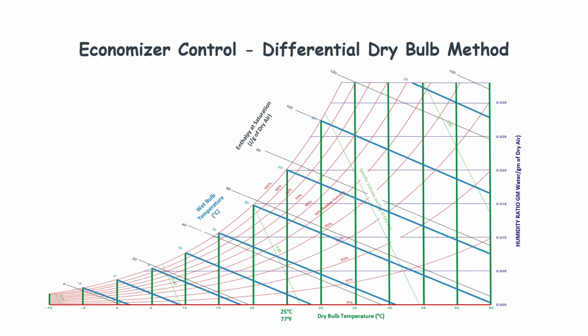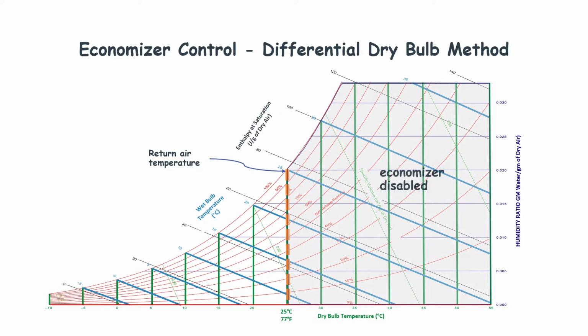The second method is differential dry bulb temperature. In this method, the controller compares the outside air temperature with the return air temperature. And if the outside air temperature is above the return air's, then the controller disables the economizer.